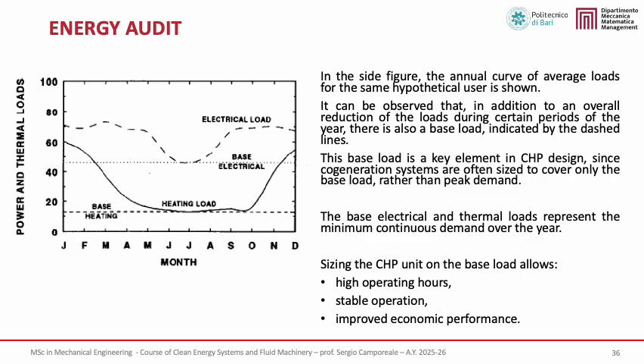It is also necessary to extend the energy audit to annual load profiles. The figure shows the annual curve of average electrical and thermal loads for the same hypothetical user of the previous slide. In addition to seasonal variations, it is possible to identify a base load for both electricity and heat, indicated by the dashed lines. This base load represents the minimum continuous demand over the year and plays a key role in CHP design.